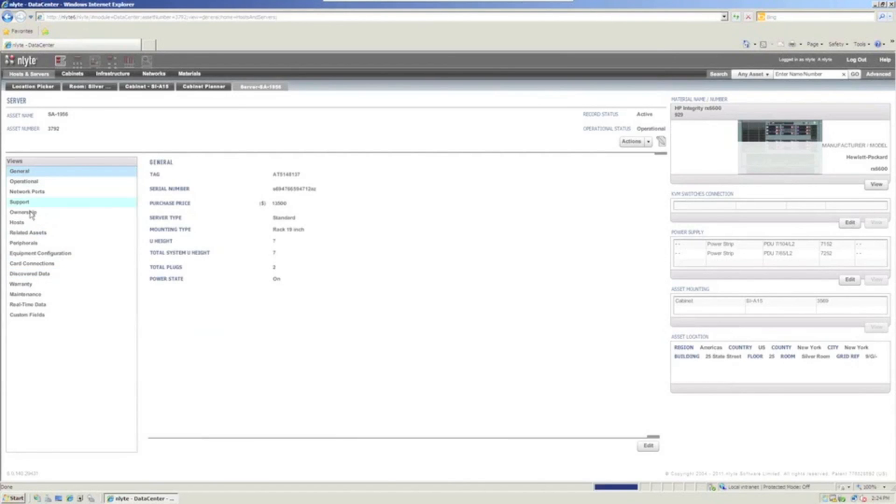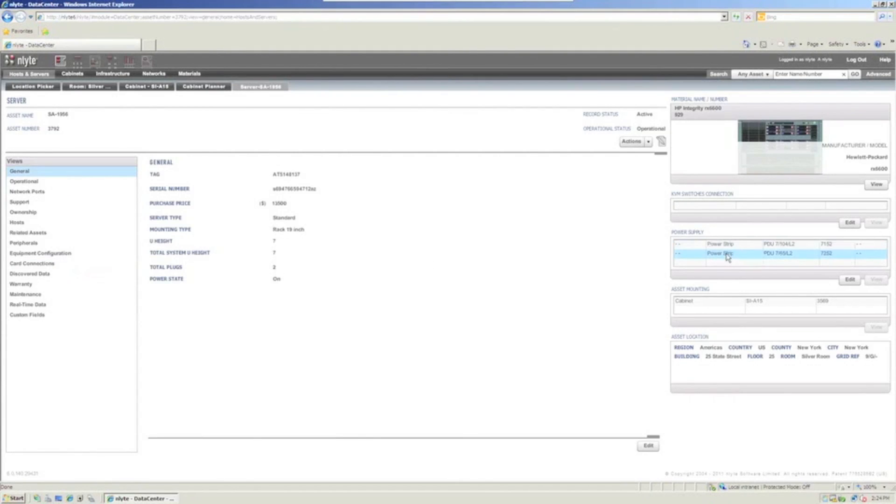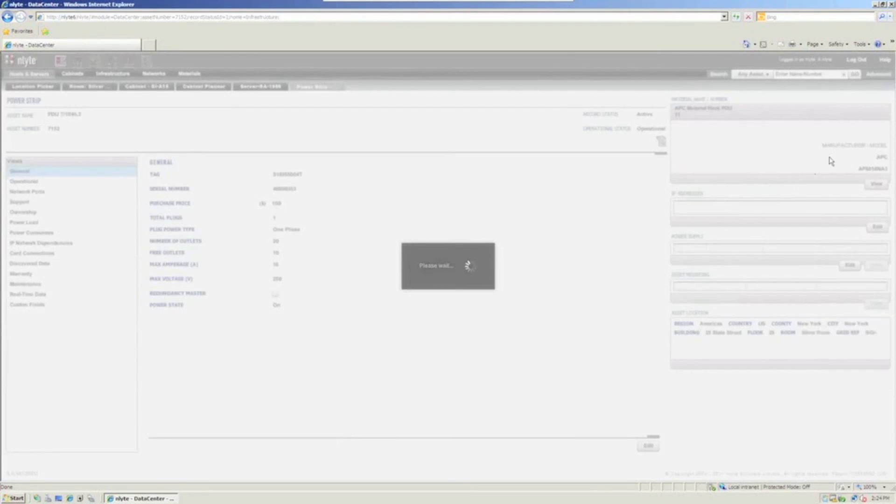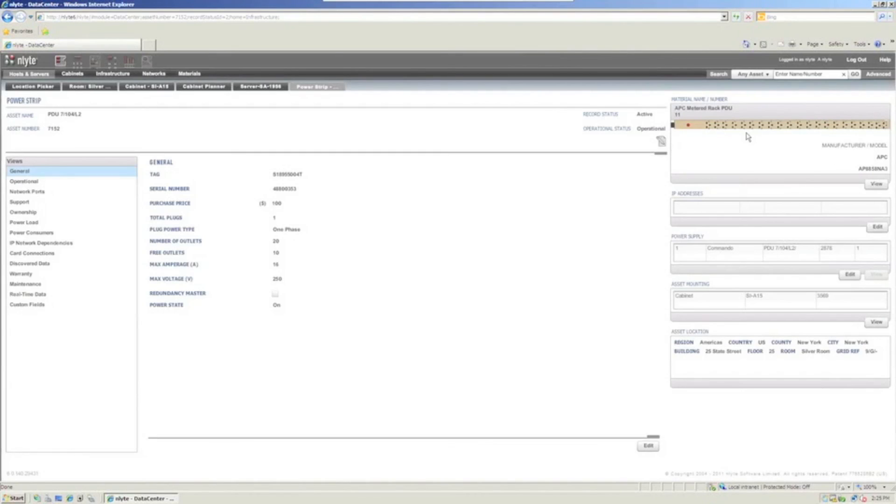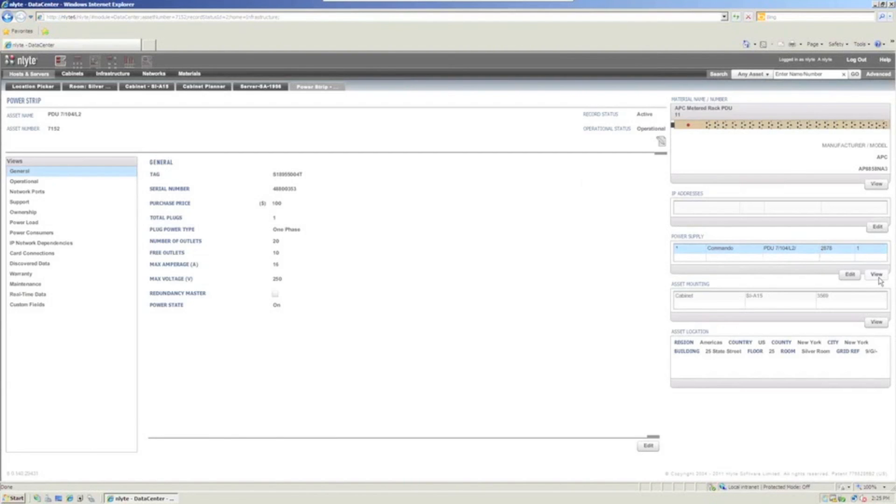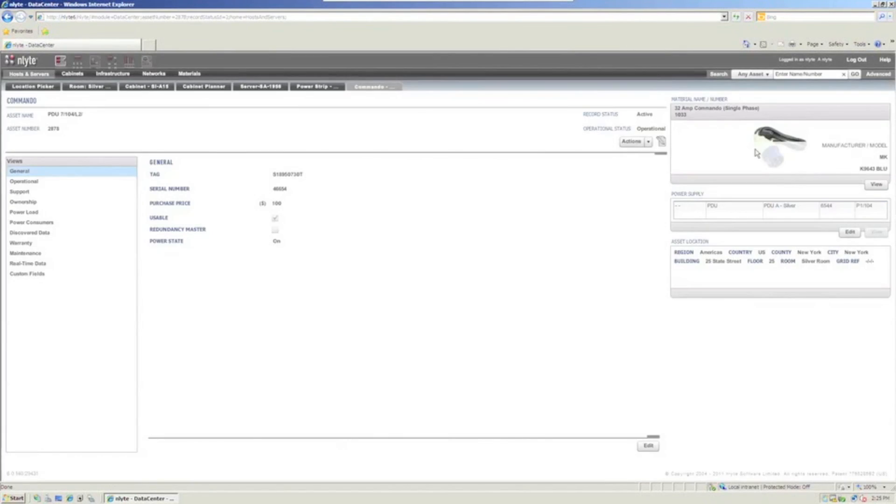If you're using the nlyte discovery tool, as most boxes will do, it brings in how much RAM you've got, what kind of CPUs and all. This is where that would display in a real world environment where you had brought in all of that other discovered data and so forth. Notice also that we mapped the entire power chain. So I know I've got this server. I know it had two plugs. In other words, I can see here are my two power strips where this particular server is plugged into. And if I view that power strip, I see what kind of power strip is it. Again, I've got the manufacturer's data sheet on that one. I can see that that power strip is plugged into a commando.